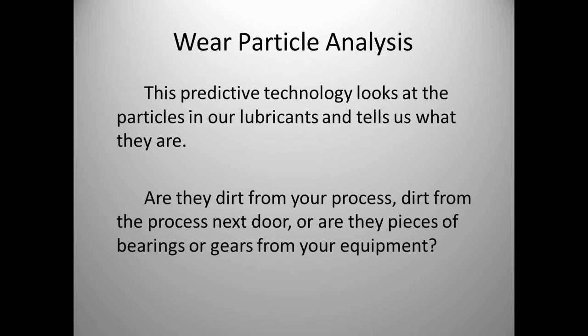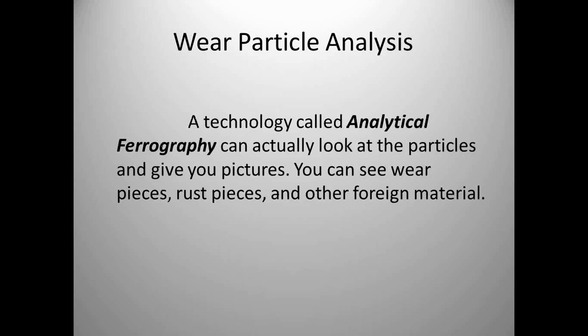Wear particle analysis looks at the particles in our lubricants and tells us what they are — dirt from your process, particles from next door, pieces of bearings or gears from your equipment. Oil analysis tells you the particle counts; this technology tells you what they actually are. It's called analytical ferrography — you get back pictures of the particles so you can see what they are. In one example from a coal-fired power plant, we could see fly ash particles and coal particles floating in the sample, as well as pieces off a bearing or gear.